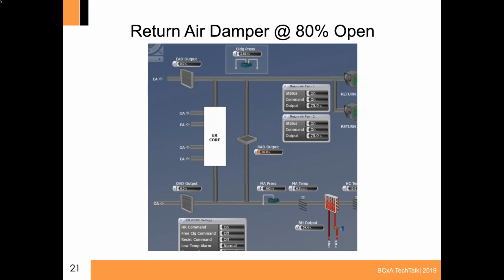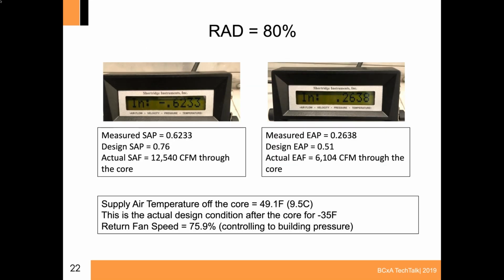However, our return fan speed is starting to decrease because we're still controlling the building pressure, and we're not going to get exactly what we need yet. So our measurements across the core, we now have increased our supply airflow up to 12,540, which is a significant increase, and our exhaust is almost at what the minimum is across that. So we had an increase in our supply air temperature off the core, but we're not quite there.